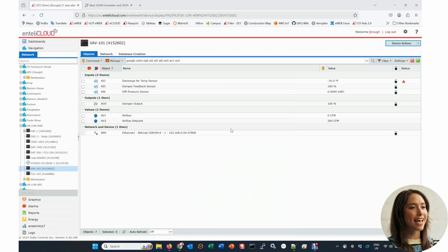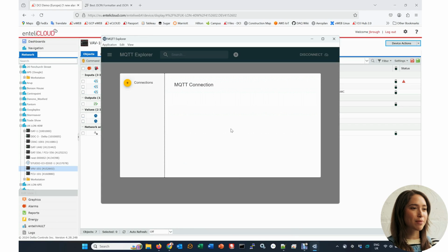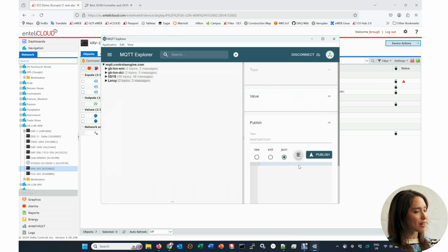First, I need to connect, so I just add the IP address or URL, check the port number. This broker has no authentication. Others may have usernames and passwords, and/or certificates and keys or tokens. The UDMI module supports these as well, but for the sake of brevity, we will not use any authentication here. So here is the view of the broker, and you can see that there are already some topics and some other data being published to it.